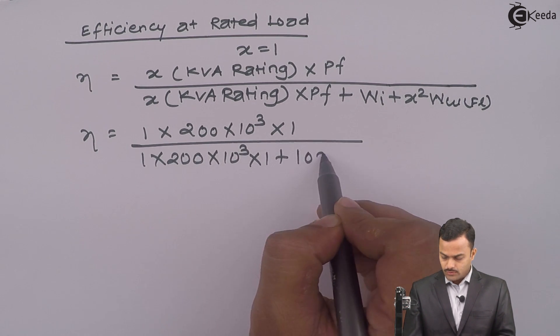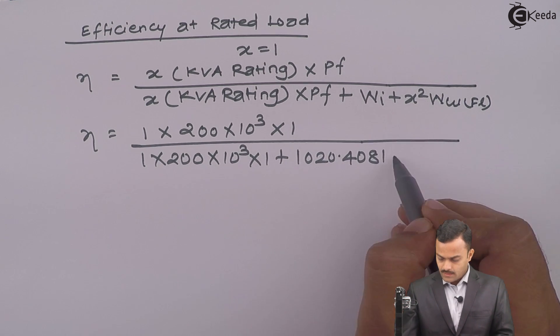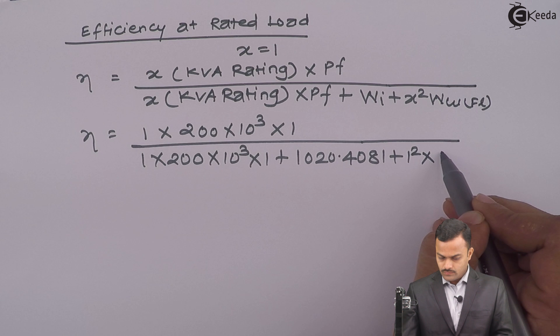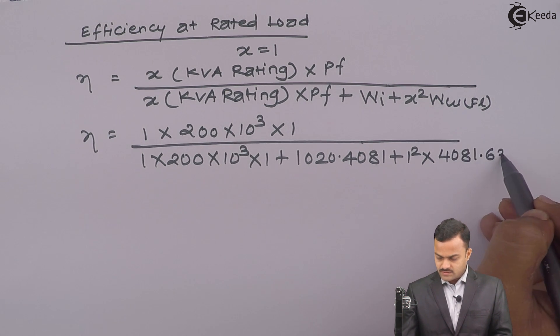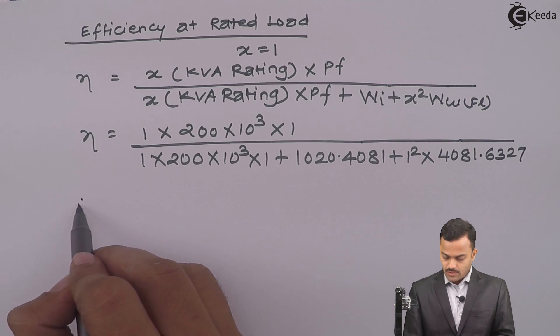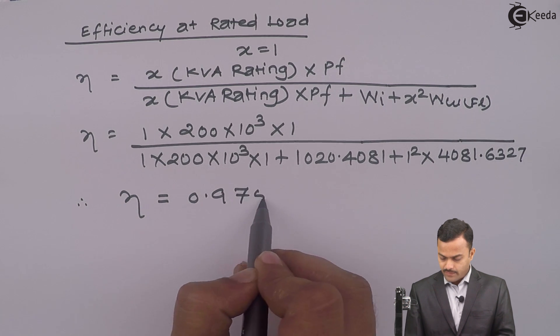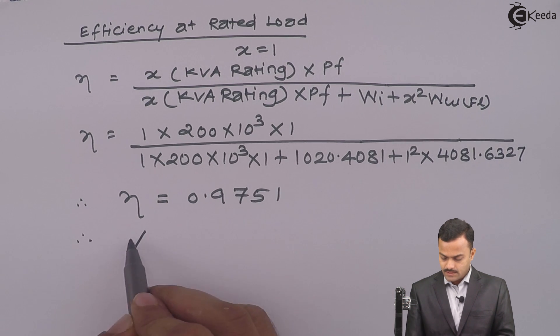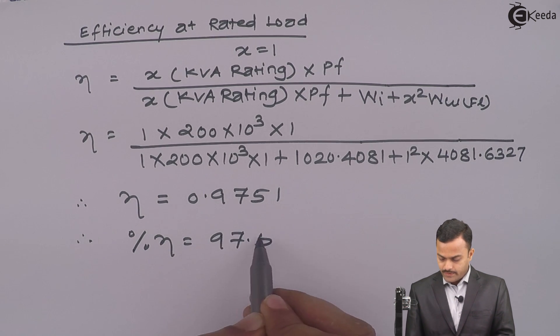So efficiency at rated load: X is 1, KVA is 200, power factor we assume as unity, iron loss we calculated 1020.4081, 1 square into 4081.6327. So if you solve this, you will get efficiency equal to 0.9751. In percentage, it is 97.51%.